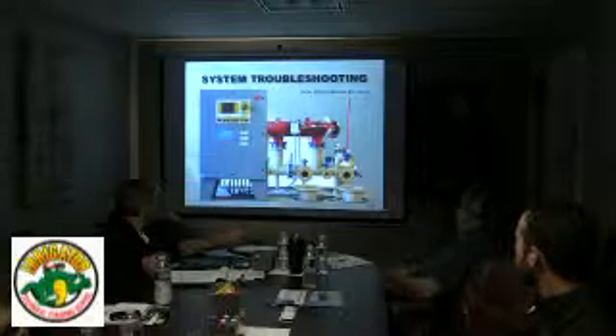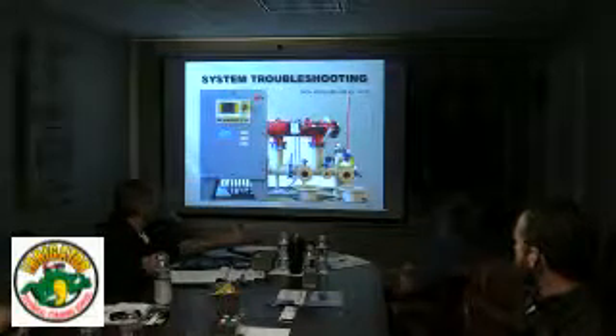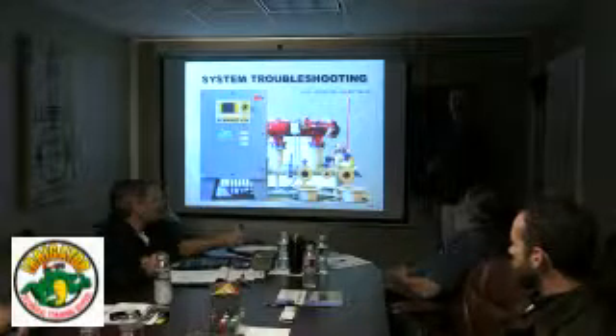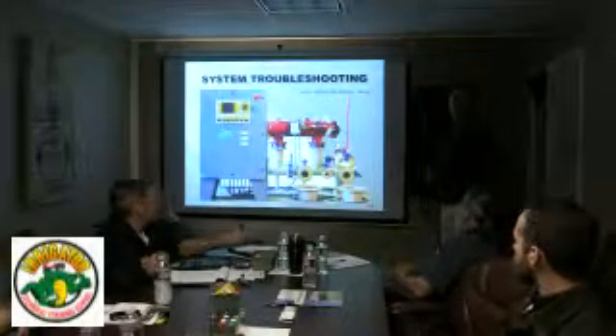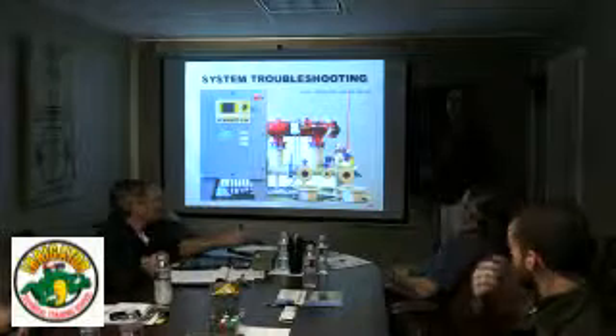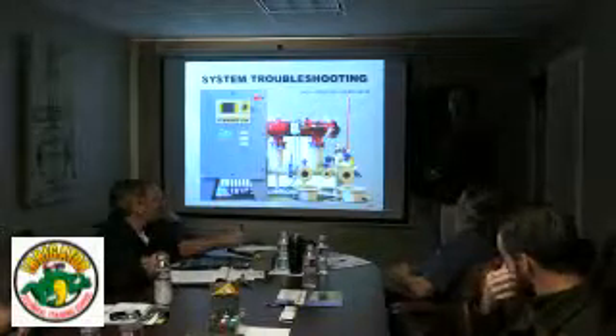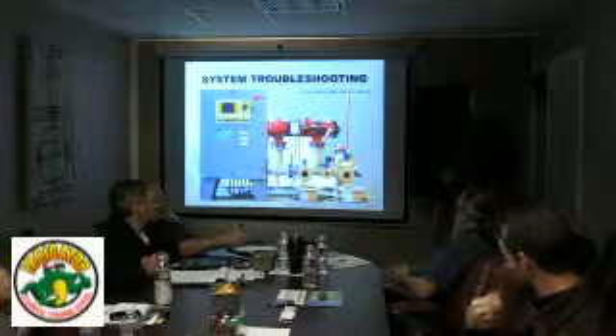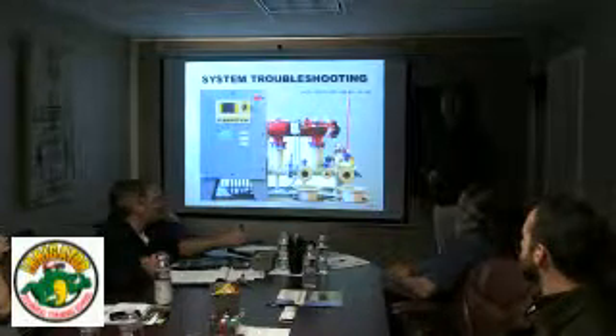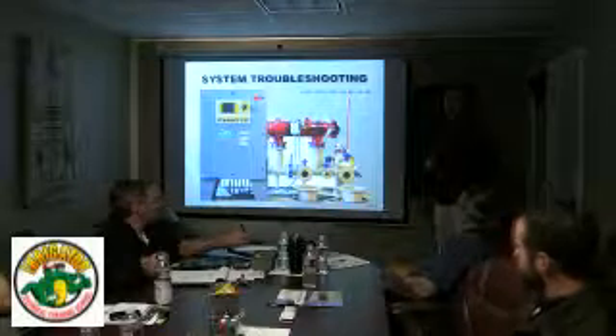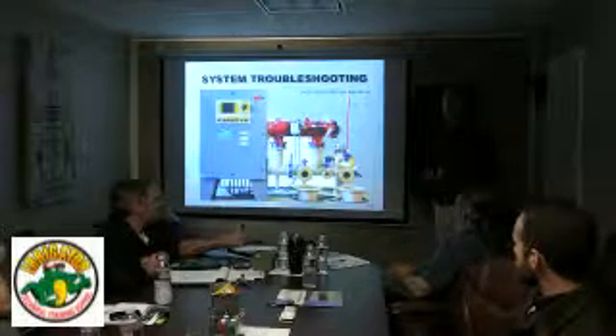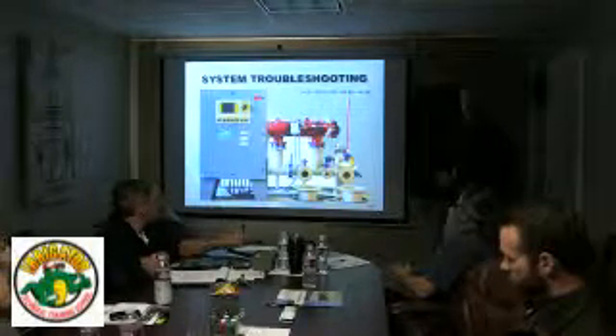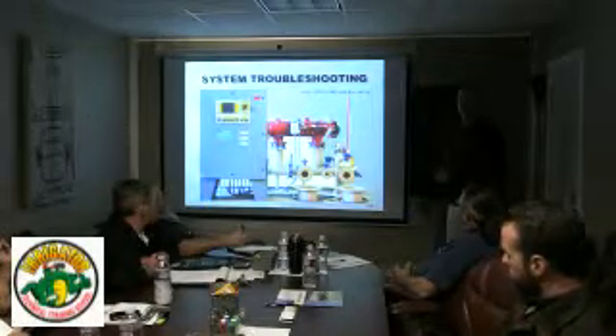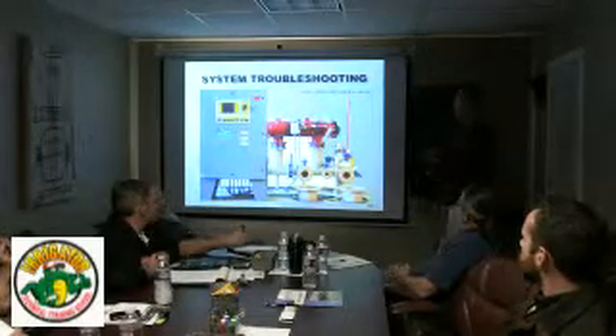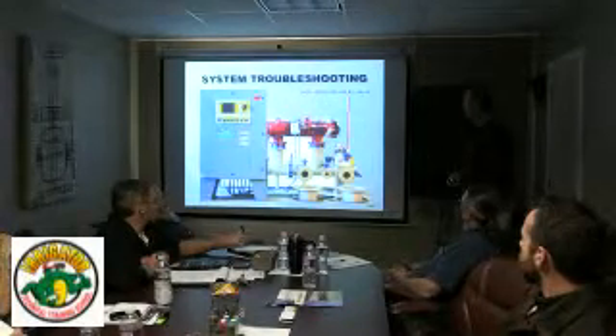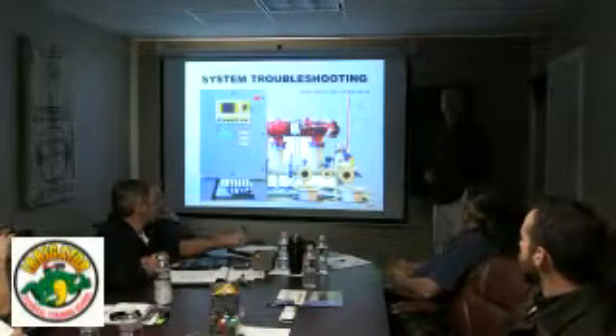Here's a Cla-Val on there. Actually, what we want is for the high pressure relief valve to be the first thing that acts. We want it to open up and relieve the pressure from any surges, and not cause a nuisance high pressure fault. So this is typically set anywhere from 10 to 20 psi above your operating pressure, and then set your high pressure shutdown in your touch screen 5 to 10 psi higher than this, and then adjust your high pressure switch for even higher than that. So hopefully this valve is just going to open and relieve the pressure, not cause any nuisance high pressure trips.